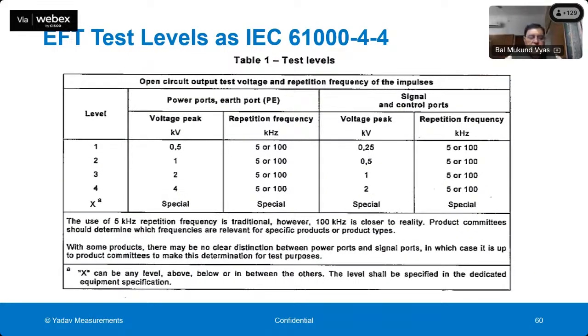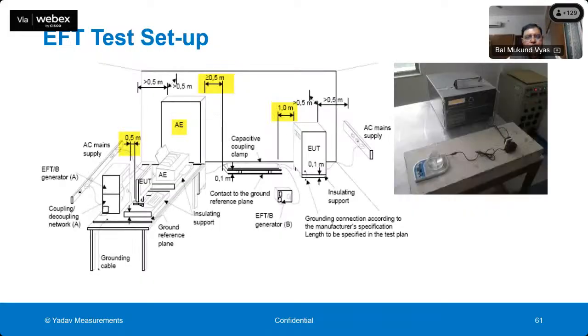These voltages can be in the range of 4 kV or sometimes even higher with respect to the earth. Both the power connection to the meter and the signal and control ports of the meter are subjected to these kinds of transients.